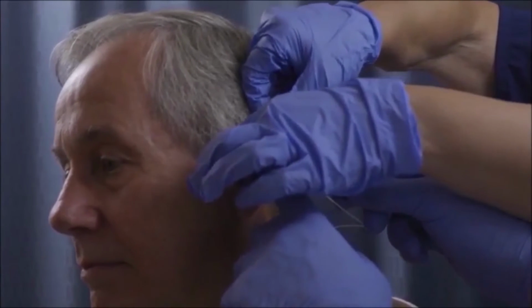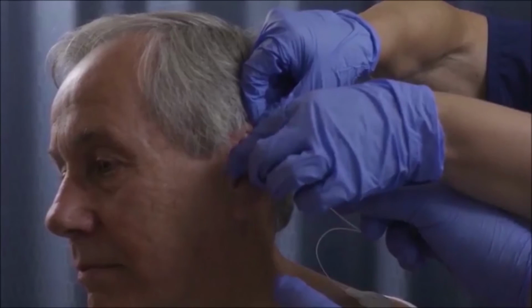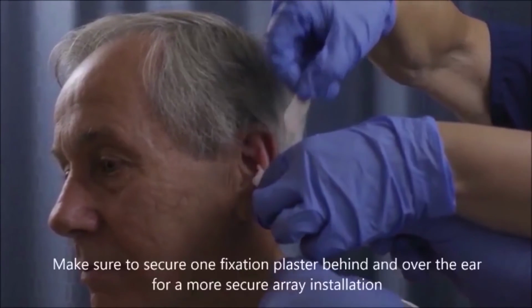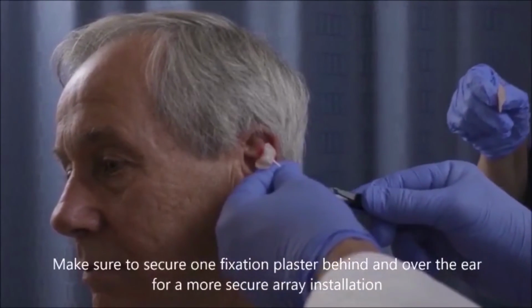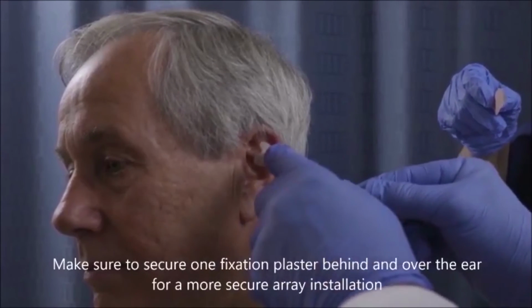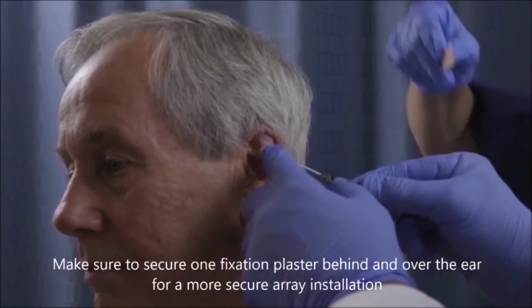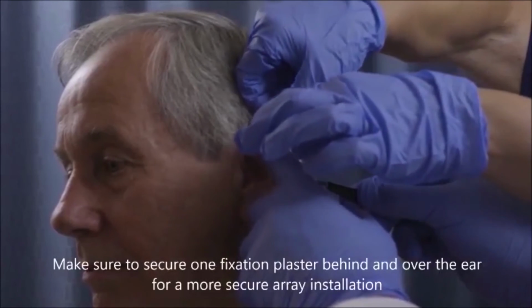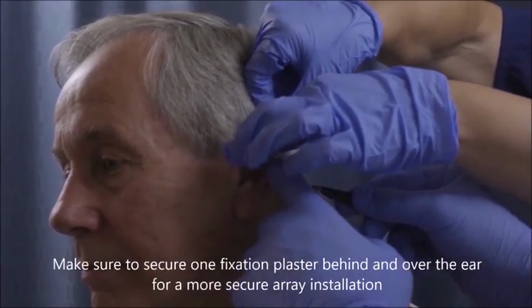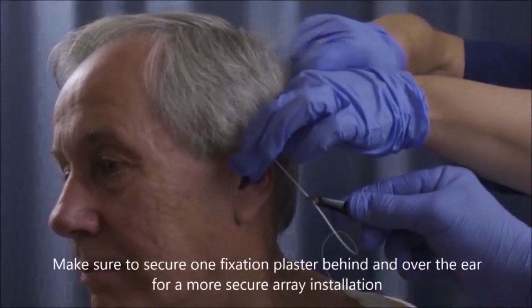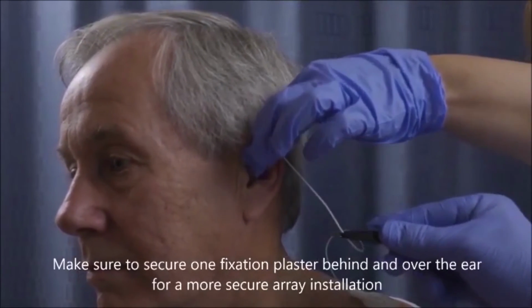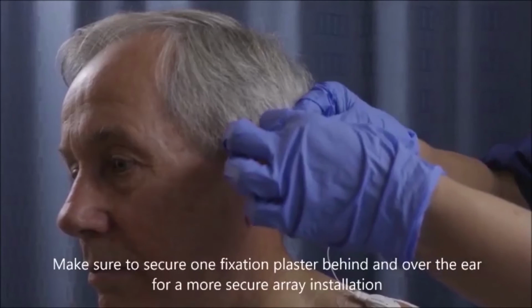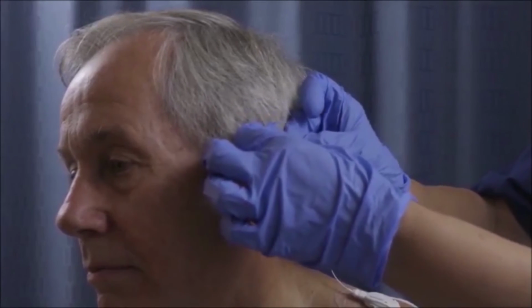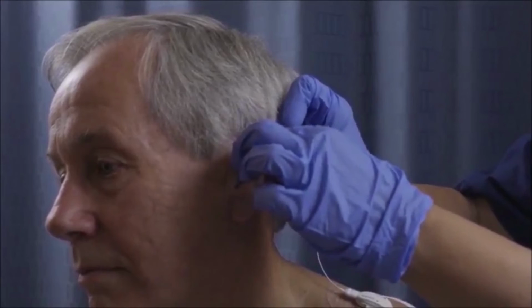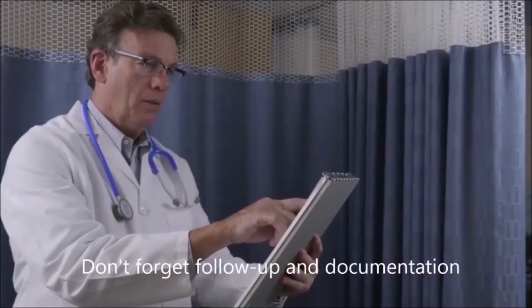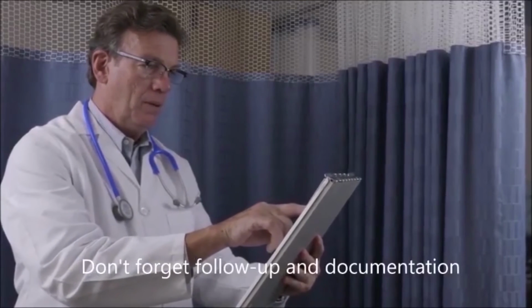Using the sterile tweezers, position the titanium needles on the array over the marked area on the ear and gently push them into the ear tissue. Once installed, take care to secure the array in 2 directions using the fixation plasters. Take care to also secure the array lead with another fixation plaster just above the shoulder clip. Adding Tegaderm to the ear and shoulder sites will add strength and help to prevent the device from becoming dislodged before the patient's next follow-up visit. Don't forget to adhere the device identification sticker to your patient records.